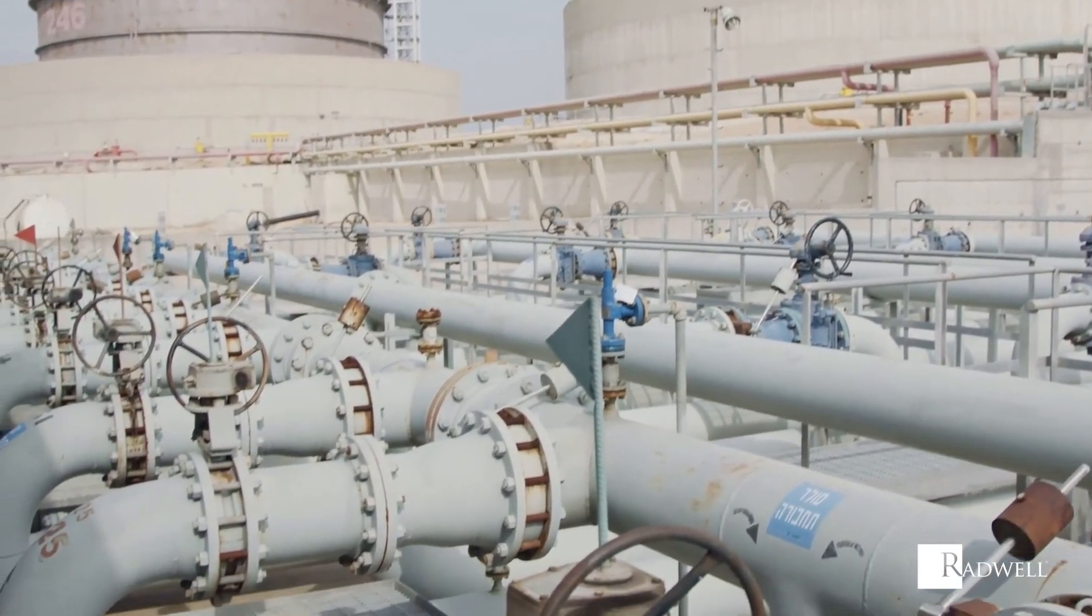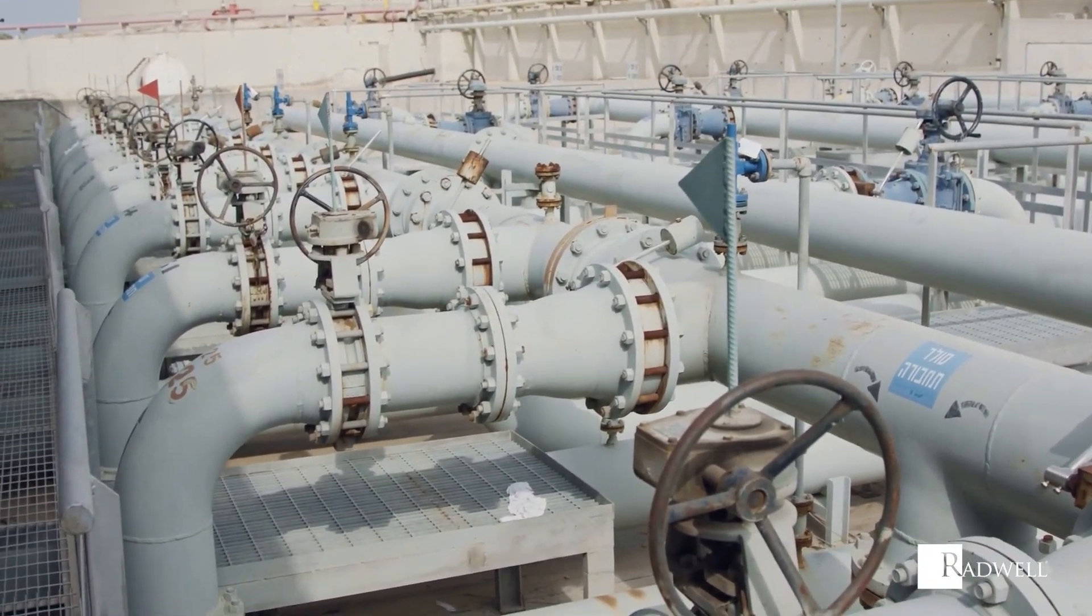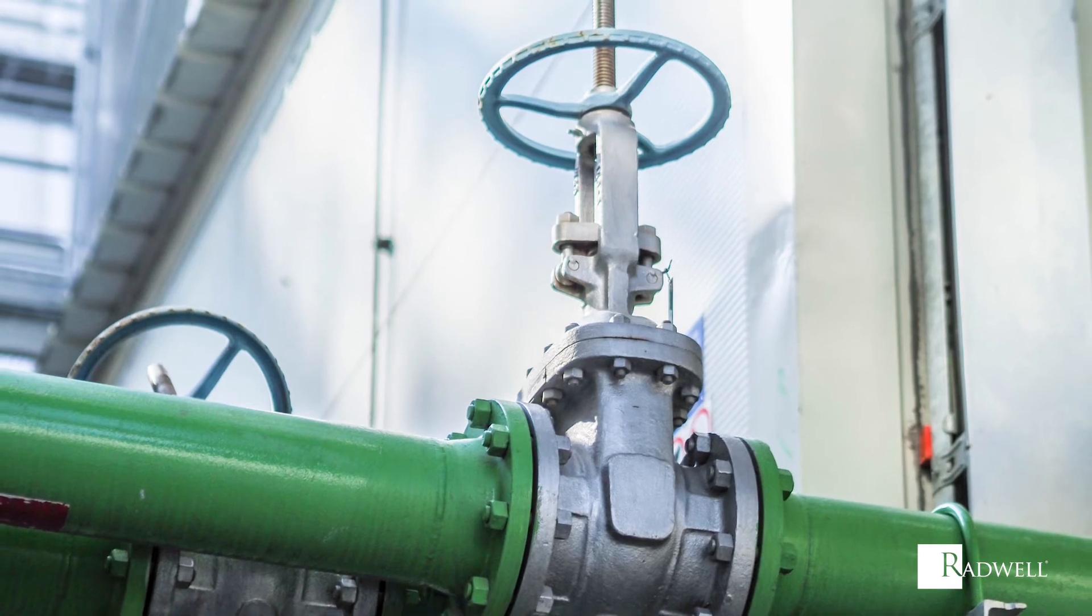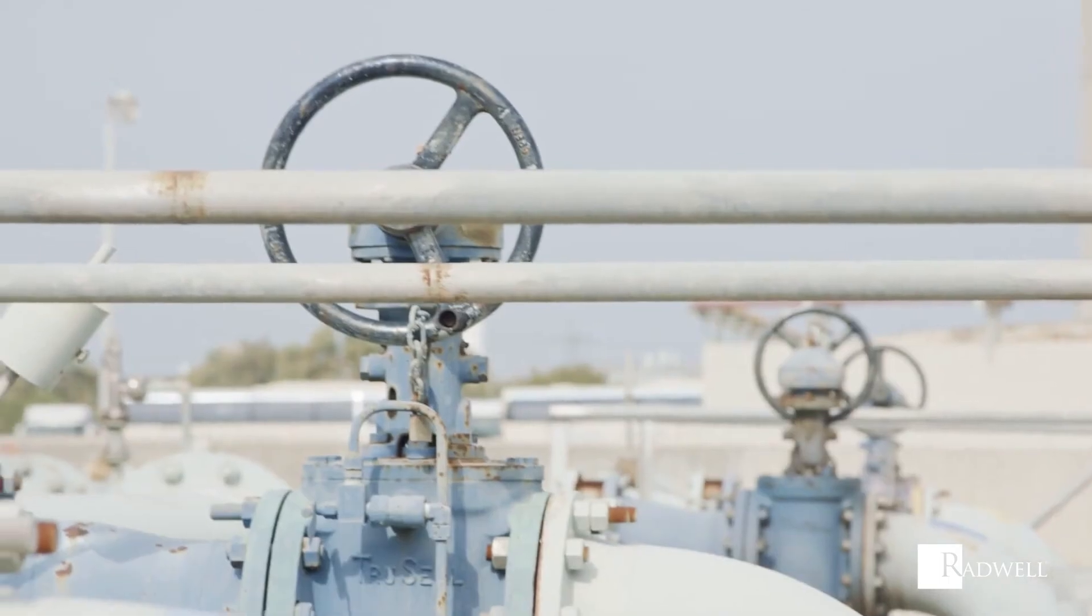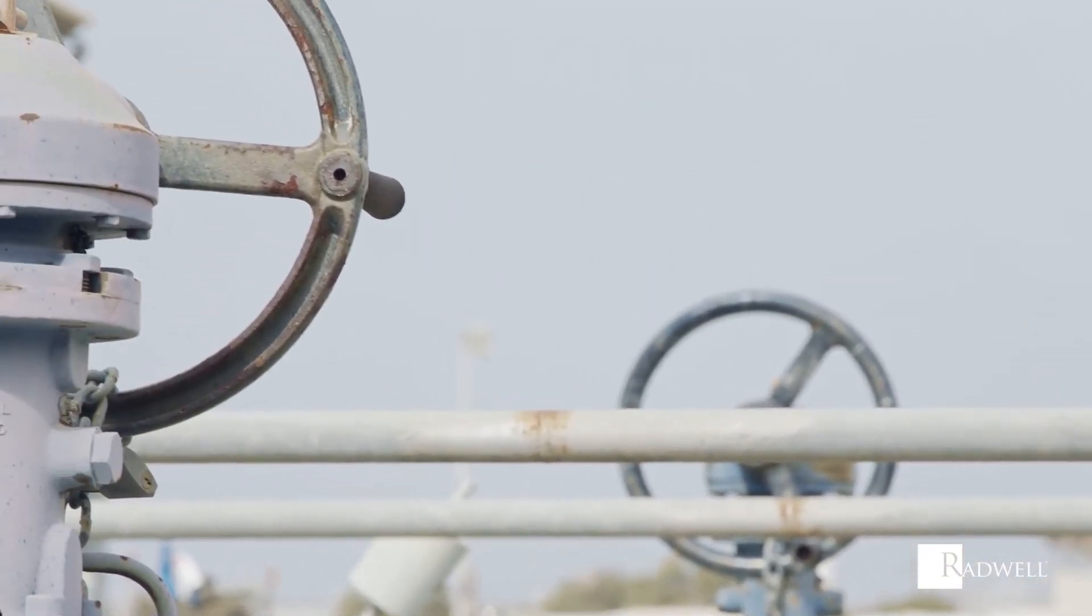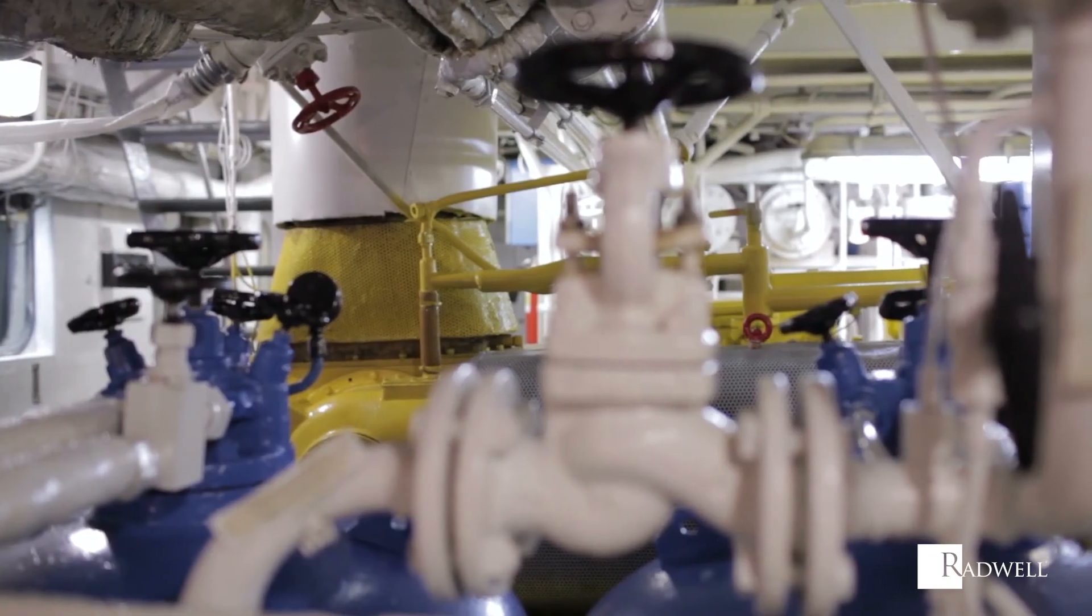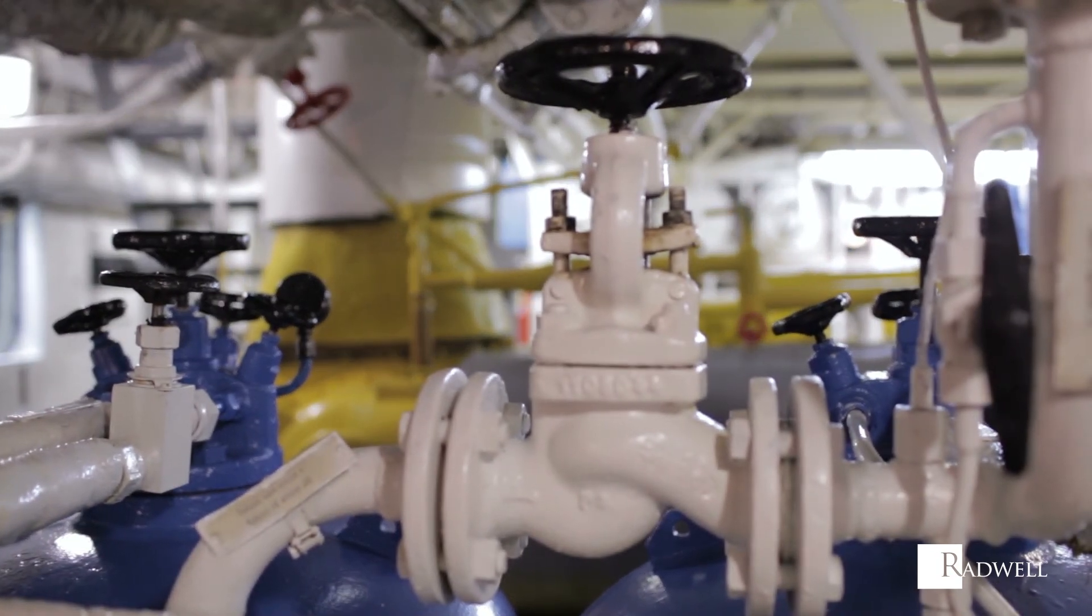How a globe valve operates begins with the hand wheel being turned. This will, in turn, screw the stem up or down. The plug or disc connected to the stem will come into contact with the valve seat, closing off the fluid flow. When lifted away from the valve seat, fluid will be able to flow through.